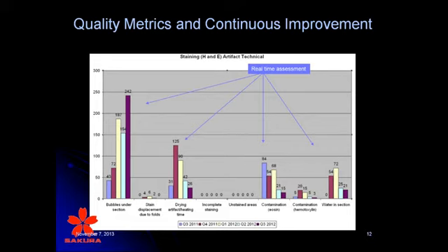And as we continue to move forward, here's what I provide to our techs on an hourly basis or a 30-minute basis whenever they want. Here we're able to identify, hey, we're having issues with this type of situation. And the funny thing is, if you look to the far left where it says bubbles under the section, what ended up happening was we received a new lot of mounting media from our vendor to find out that they changed people that were creating the mounting media, which in turn changed the way our refraction was for our digital pathology, as well as the amount of bubbles we get.